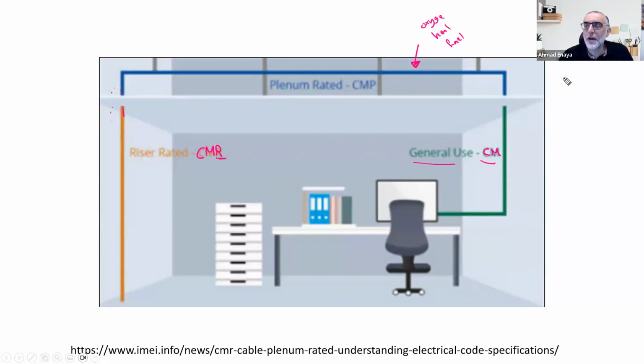Airflow and oxygen, yeah, because we have the airflow that goes between rooms in the same building, and in many cases, the airflow is circulating over this plenum. So if we have any fire here, it can easily spread to the other rooms on that floor and even go between floors. But the difference between riser and plenum is that here we have a lot of airflow and a lot of oxygen, which means it is the best location for fire to spread. If this cable jacket represents the fuel, if it is combustible, so we have the oxygen, we have the fuel.